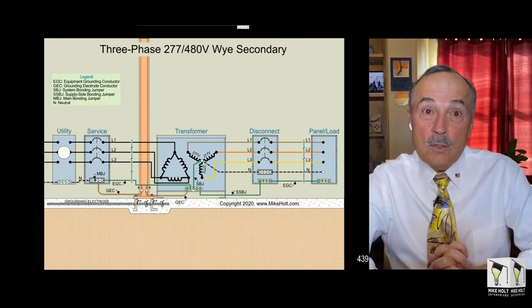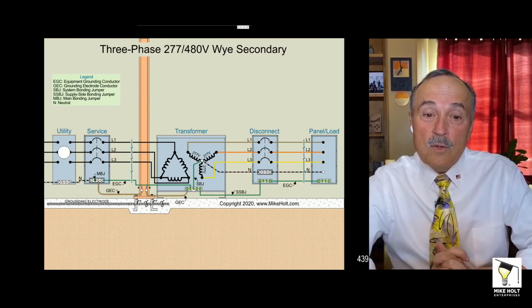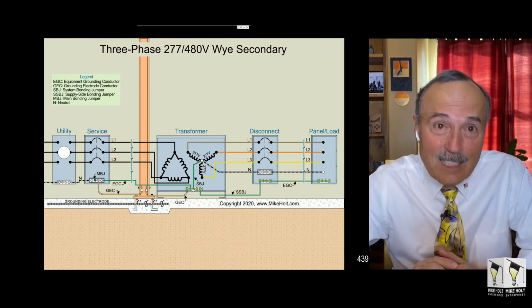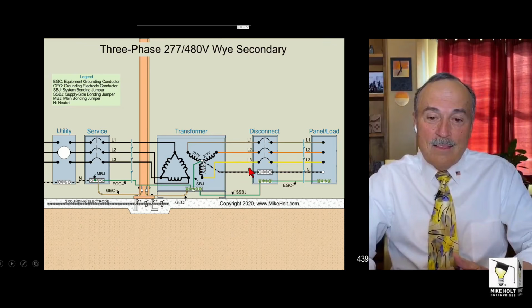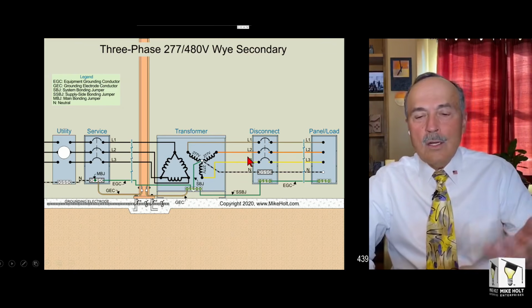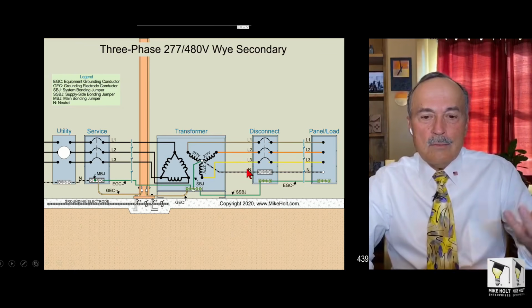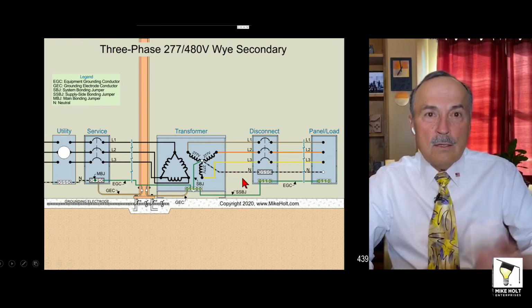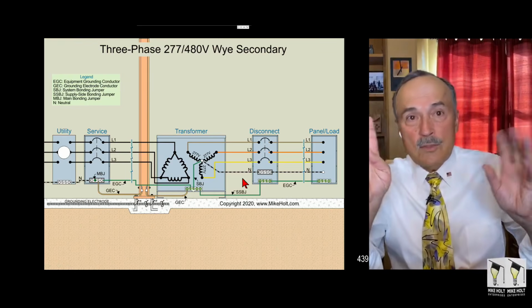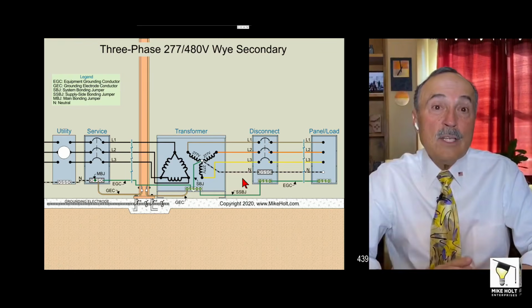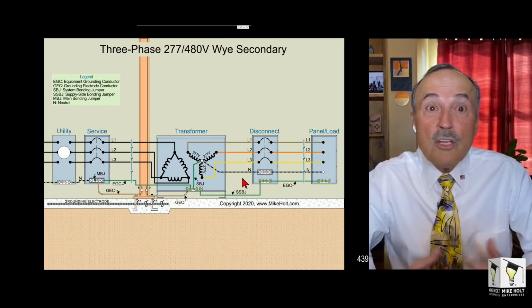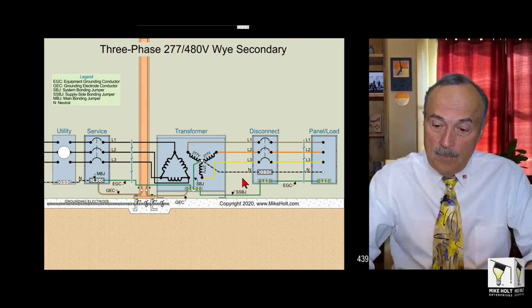Okay, we've got a 277/480 volt, 3-phase, 4-wire wye system. Right, 1, 2, 3. What color code? Oh, brown, orange, yellow. Code doesn't really care. Brown, purple, yellow, because you're thinking orange can't be used for the high leg, so you put purple. Doesn't really matter. You can use orange. You can use purple. You can use any colors you want to.